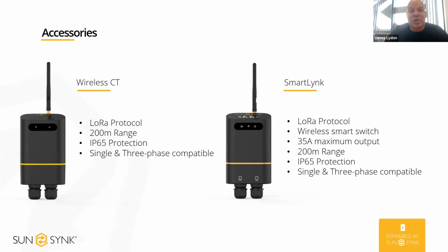Similar to the immersion diverter, but this could be connected to a hot tub or anything, so that you can set on the inverter: okay, we're exporting power, we want to divert it to this hot tub, and the system will automatically do that. It will turn the SmartLynk on, and it will give it the power that it needs.